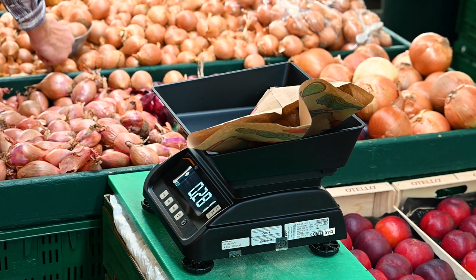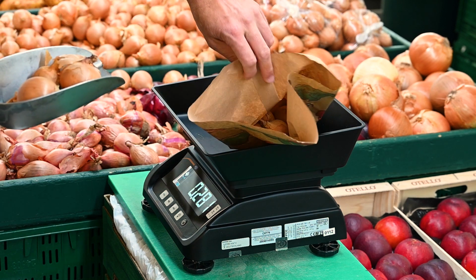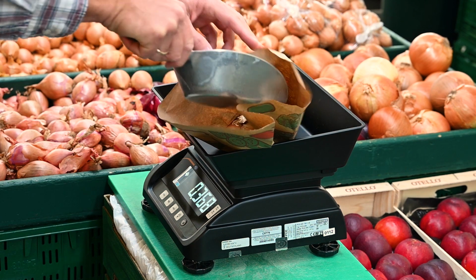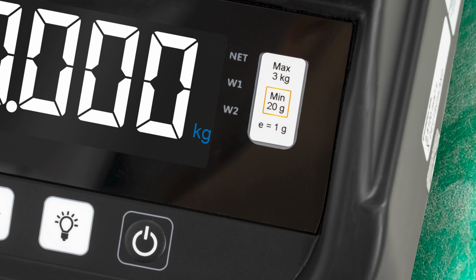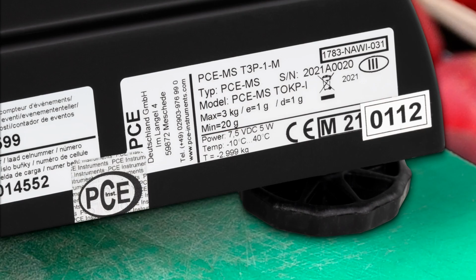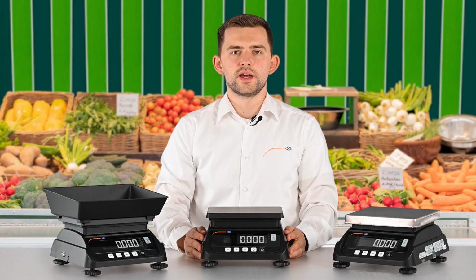In the area subject to legal control, weighing must be carried out above the specified minimum load. The minimum weighing weight is shown on the display and on the identification plate. For the PCE-MS T3, the minimum load is 20 grams. When weighing below the minimum load the scale shows a value, but it is not permitted to use these weighing values for legal purposes.